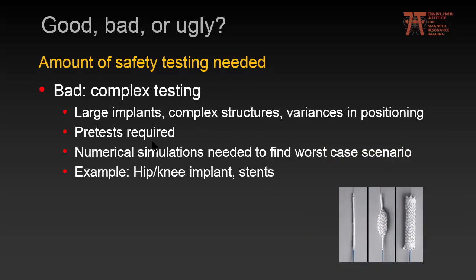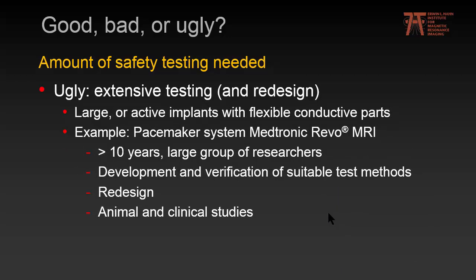Bad implants need complex testing — usually some pre-tests and long-lasting numerical simulations to find a worst-case scenario. These are typically large implants with complex structure that may vary in positioning, such as stent grafts, whose structure is quite complex and looks different when inflated in the body compared to when taken out of the packaging. Ugly implants need extensive testing and maybe even redesign — these are large or active implants with long, flexible, conductive parts. An example is the Medtronic Revo pacemaker system, the very first MR-conditional pacemaker, which took a large group of researchers more than 10 years to bring to market.